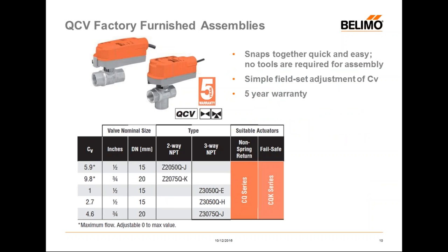The QCV product range consists of two two-way valves. The maximum CV for the half-inch is 5.9 CV and 9.8 for the three-quarter inch. For the three-way valve, there are three individual CVs: one, 2.7, and 4.6. The asterisk on the CV value indicates that these valves have the ability to adjust flows in the field. The QCV valves snap together quickly and easily — no tools required for assembling actuator to valve — with simplified field adjustment of CV, covered by a five-year warranty.